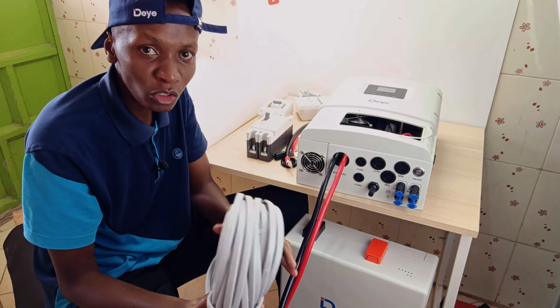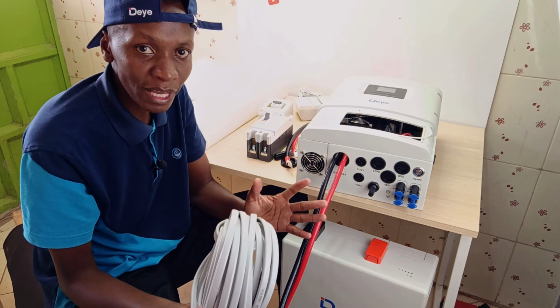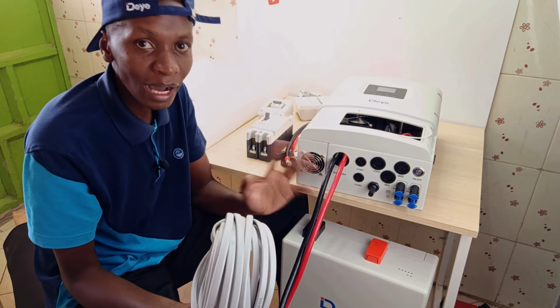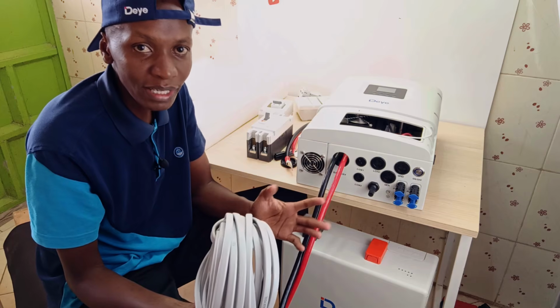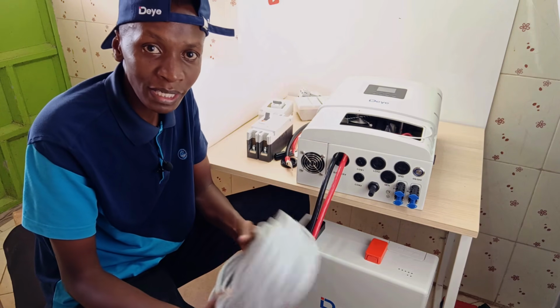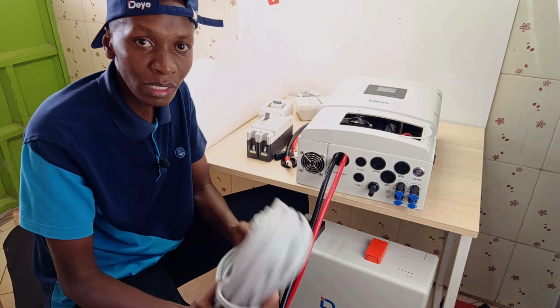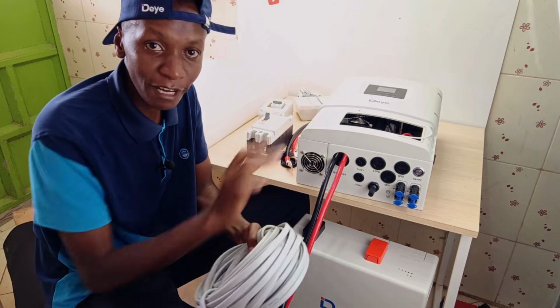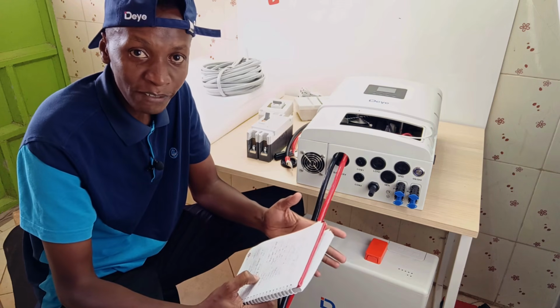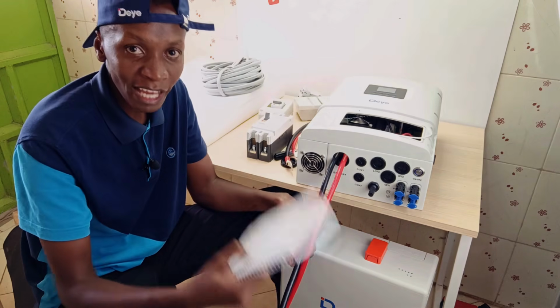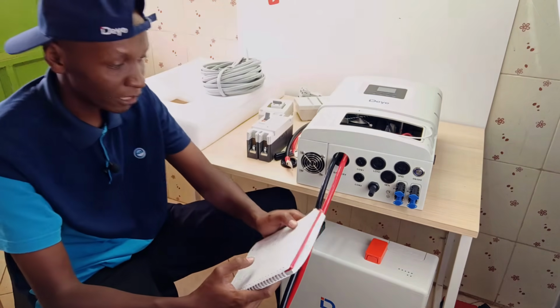I won't connect everything to my backup loads. I will select a few circuits, like for example the socket outlets and the lights as my backup loads. Everything else that requires heating, like the water heater in the shower and the cooker, they won't be connected to this inverter. Let us now go through all the important specifications of the inverter and the battery, and I have my notebook here with all the specifications.